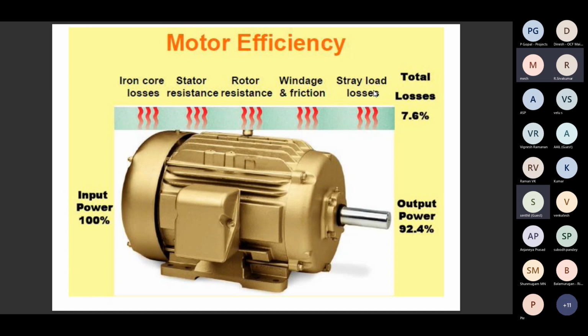If you take, for example, a 50 HP motor, with an IE3 motor the efficiency is almost 92.4%. The same motor can be replaced with IE4, and the efficiency figure may be 94.2%. Another 1.8% more output can be achieved, with 1.8% less losses. But the cost of an IE4 motor compared to IE3 is quite high. So based on the application and usage, the foundry can decide whether to go with IE2, IE3 or IE4. For example, if a particular motor runs for only 2 hours per day, installing IE4 is very expensive. Maybe you can install an IE2 motor for that particular section.